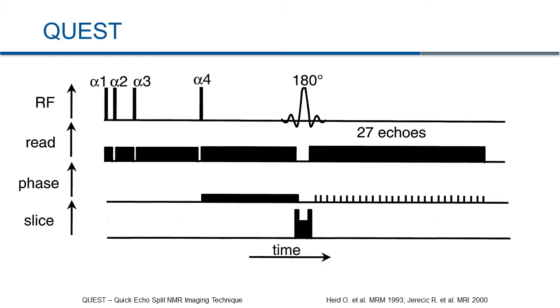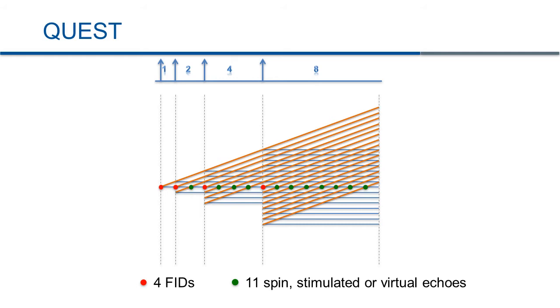For reducing the RF energy in the pulse sequence, we chose QUEST as a template to build our sequence. QUEST represents Quick Echo Splitting MR Imaging technique. It was proposed in the early 90s and tried to replace EPI sequences. QUEST uses the minimum number of RF pulses to acquire the maximum number of signals, so it can reduce SAR dramatically. If the gaps between the RF pulses increase as 1, 2, 4, 8, as shown in this slide, we can use the phase graph to show the number of signals. With 4 RF pulses, it can generate 4 FIDs (red dots) and 11 high-order echoes (green dots).